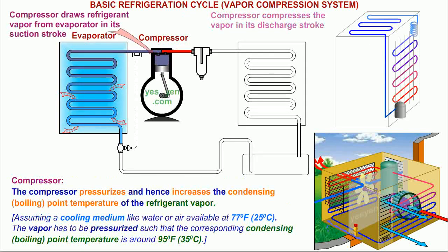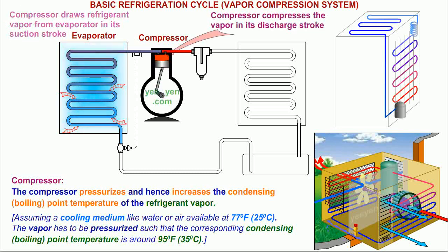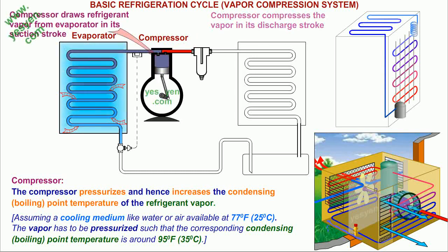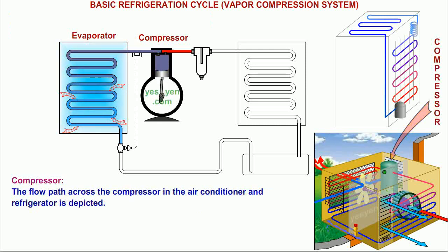Compressor: The compressor pressurizes and hence increases the condensing — that is boiling point temperature — of the refrigerant vapor. Assuming a cooling medium like water or air available at 77 degrees Fahrenheit or 25 degrees Celsius, the vapor has to be pressurized such that the corresponding condensing, that is boiling point temperature, is around 95 degrees Fahrenheit or 35 degrees Celsius. The flow path across the compressor in the air conditioner and refrigerator is depicted.